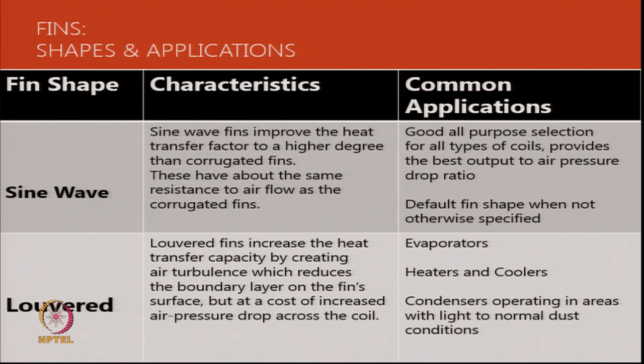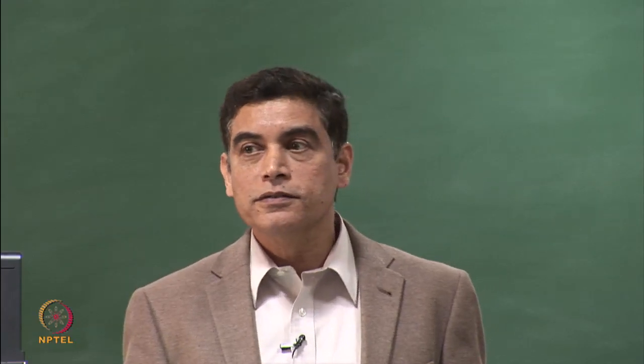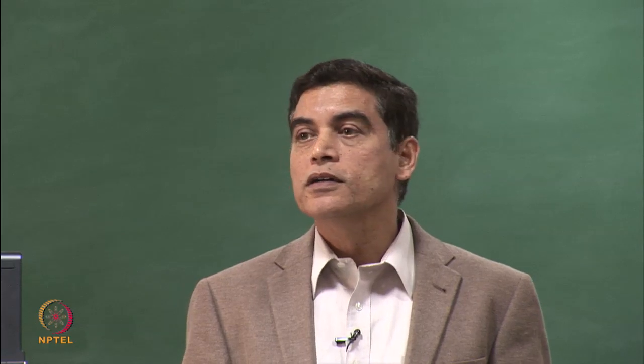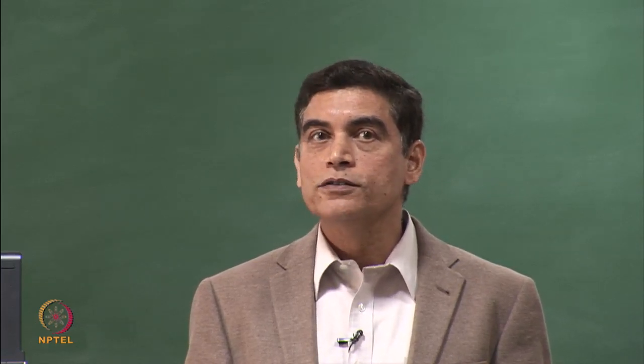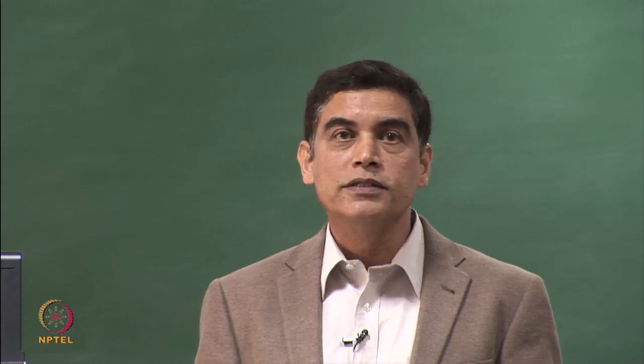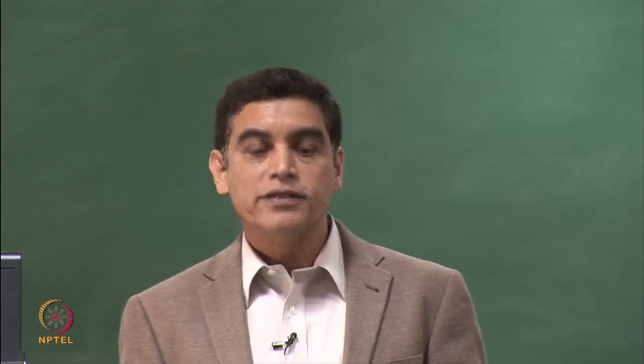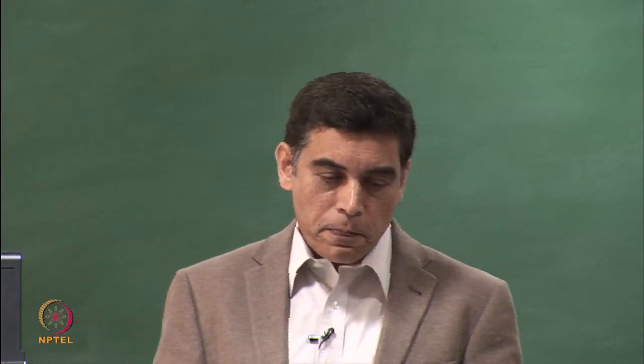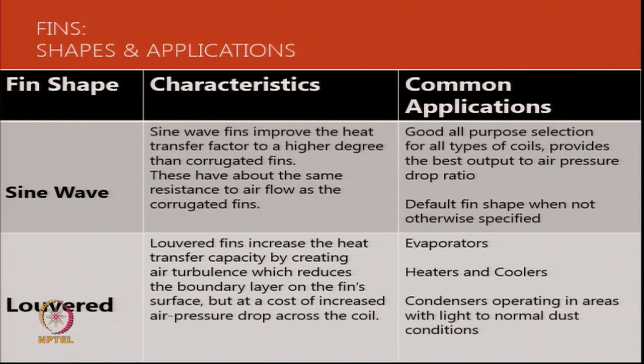There have been two fin forms in the market for reasons of some patents. Someone filed a patent for a particular shape of this fin, a sine wave fin with and without lancing, and for that reason it was protected, and therefore people tried to beat that by making a louvered fin. So there have been two fins in use, louvered and sine wave, pretty close to each other, but the sine wave has a better heat transfer than the corrugated fin. The corrugated fin, not the louvered, the corrugated fin. And then the sine wave is again a general all-purpose selection. When you are bothered about clogging, it is less prone to clogging than a louvered fin, and it is also the default fin shape. If we are not specifying anything, then this could be the default fin shape that we use.